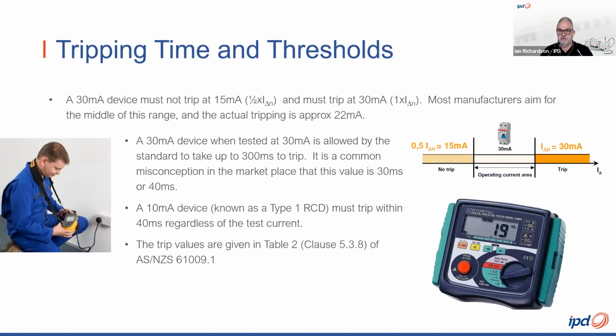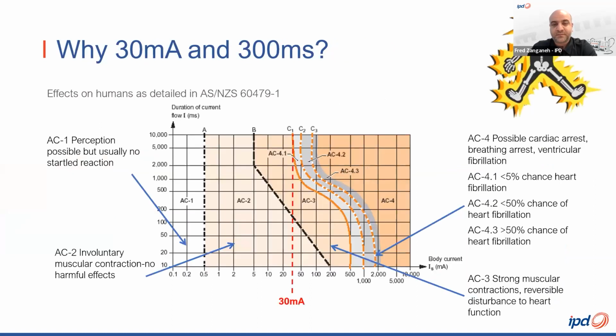You know, it's a common misconception in the market that this value is 30 milliseconds or 40 milliseconds. It's not actually correct. The standard also defines the sensitivity and time of operation for RCDs. The requirement is a tripping time on a sliding scale: 300 milliseconds at 100% sensitivity, as I just said, 150 milliseconds at 200%, and 40 milliseconds at 5 times the sensitivity, or 40 milliseconds thereafter. Also, there is an exception, which is a 10 milliamp device known as type 1 RCD, which must trip within 40 milliseconds regardless of the test current. The trip values are given in table 2, clause 5.3.8 of AS/NZS 61009.1, and you can check it there if you want more information about them as well.